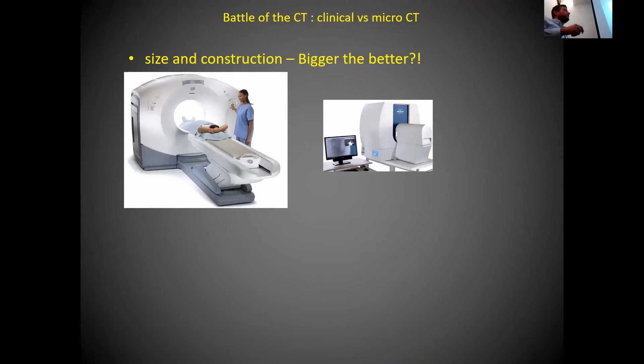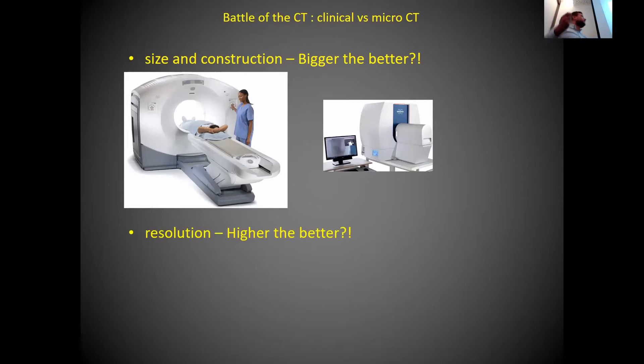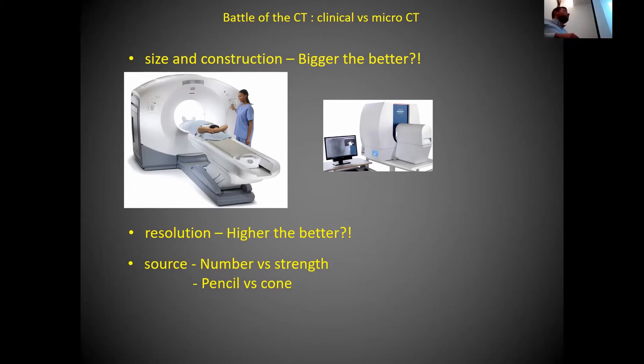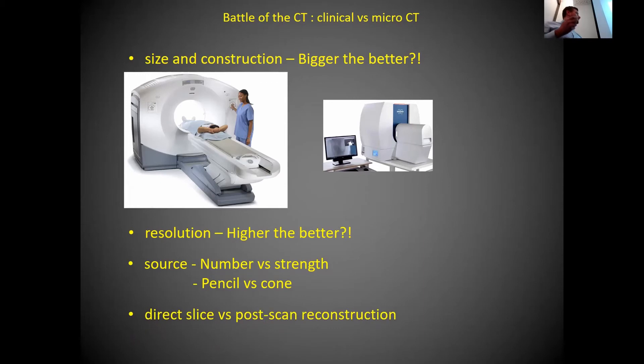Some differences between clinical and micro-CT: in terms of size, most micro-CT scanners are benchtop models — you can have them in your lab without needing a separate room or dedicated technicians, but they are smaller and limited by sample size. Micro-CT has higher resolution but at the cost of higher radiation. Modern clinical CT scanners are multi-slice with multiple detector rows, while micro-CT has a single cone-beam source with one detector. Clinical CT uses a pencil-shaped source.